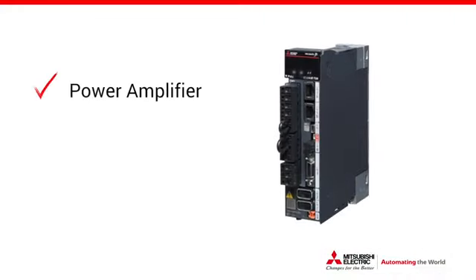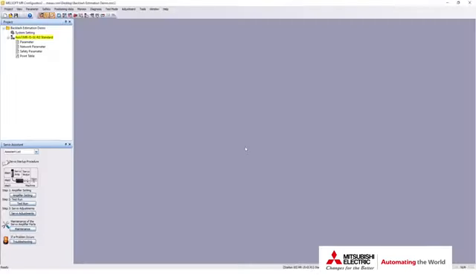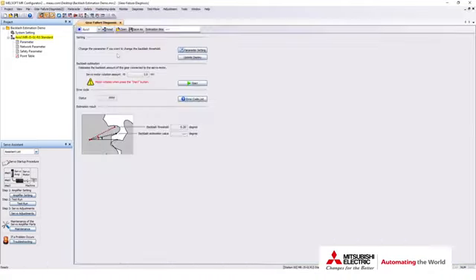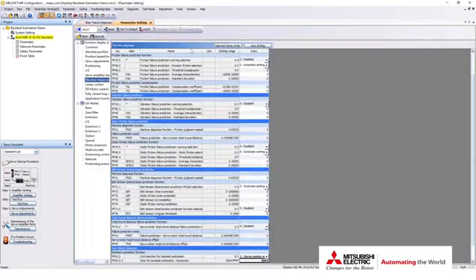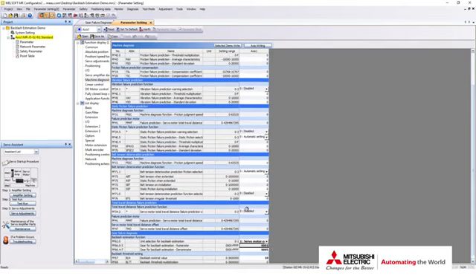Start by powering on your amplifier and connecting your amplifier to your PC with a USB cable. Open MR Configurator 2 and switch to online mode if it didn't switch automatically. Under the diagnosis tab, select gear failure diagnosis to open up the estimation function. Click the parameter settings tab and adjust the parameters to fit your application. Refer to the manual for details on how to set these parameters. Write your parameters to the drive and cycle the power.